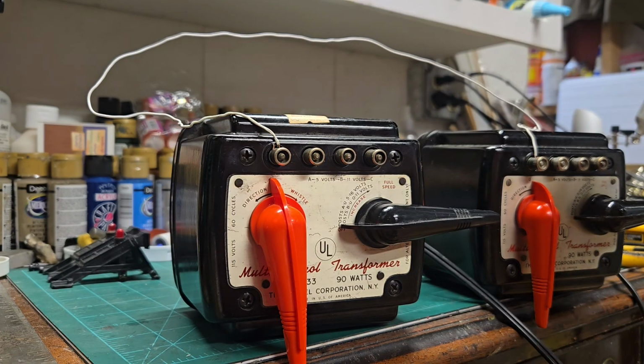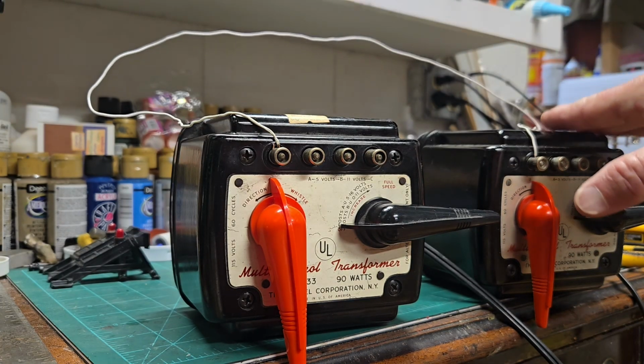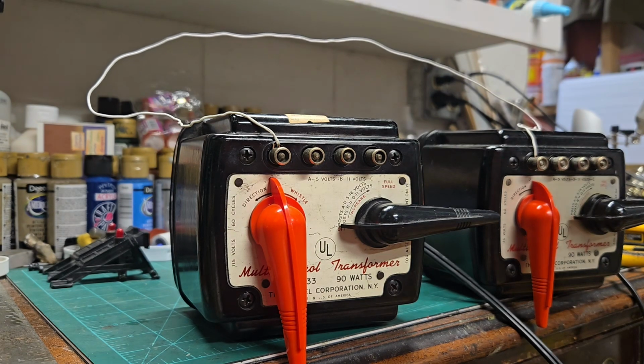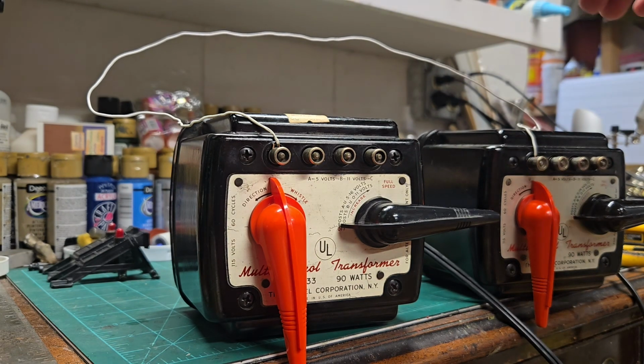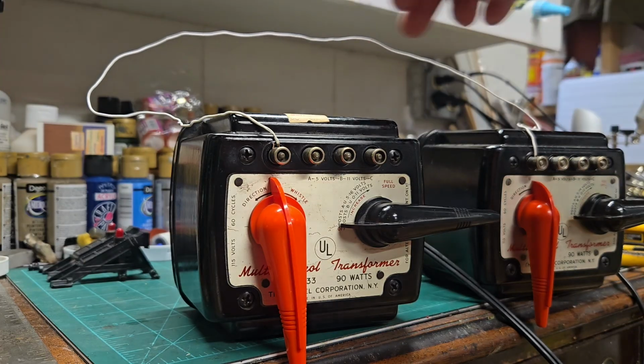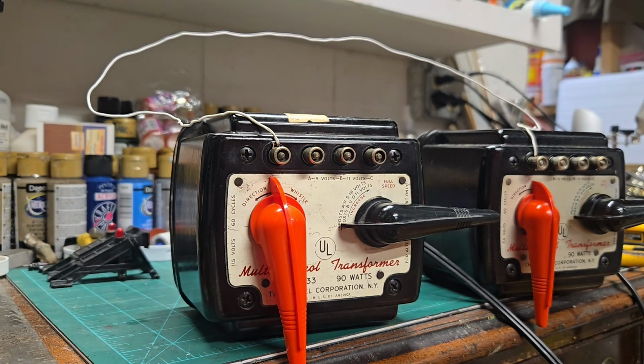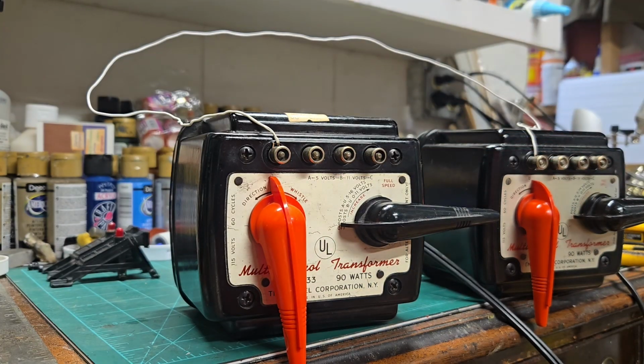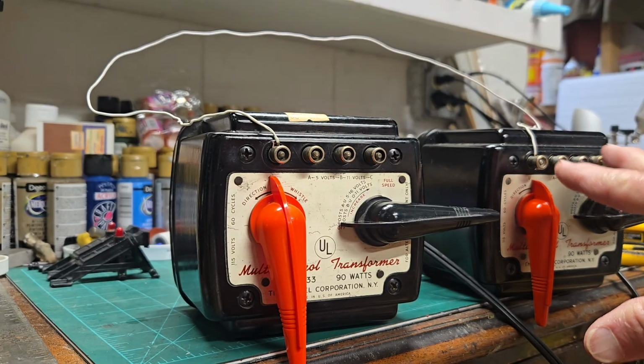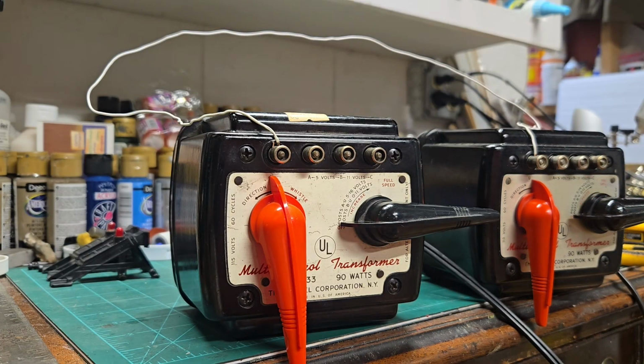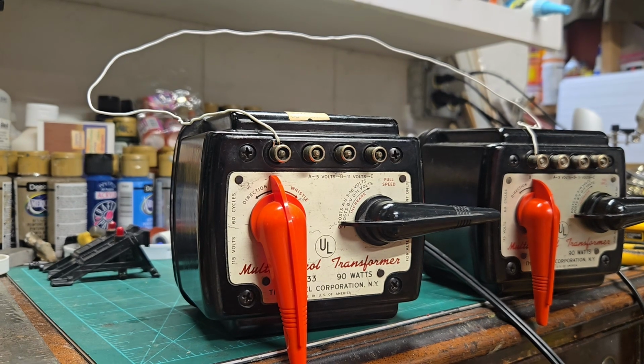Phasing the new transformer - this particular 1033 transformer is probably not the best to use when phasing with other transformers, unless you're phasing it with another 1033, in which case you'll probably be all right. I haven't checked all the terminals, so you'll want to check me on that. Even if these were phased, I don't know if this transformer would still have a problem between transformers having a common connection when using both the fixed and variable settings. I wanted to clarify that and thought it was important to point out.